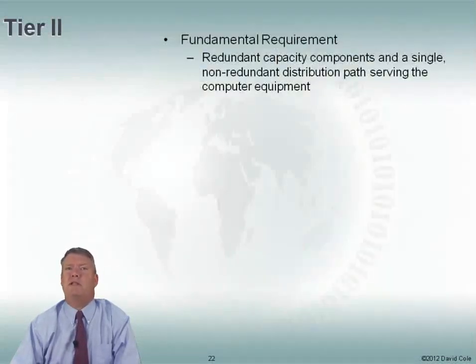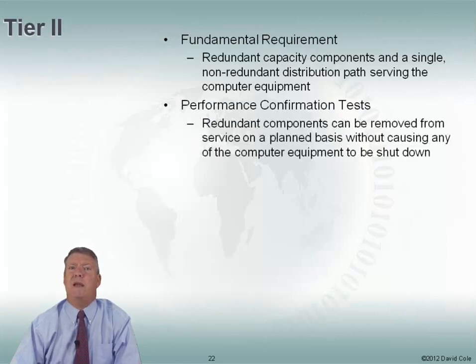Let's look at Tier 2. Here we add a redundancy component: redundant capacity components. So if I have a computer room air conditioner for cooling, I have a spare in case one of my cooling units goes down. I've added redundancy in my components, but I still have a single distribution path, only one electrical path for my equipment.